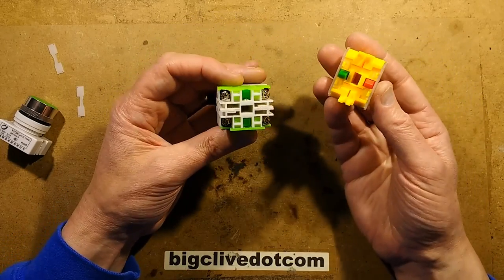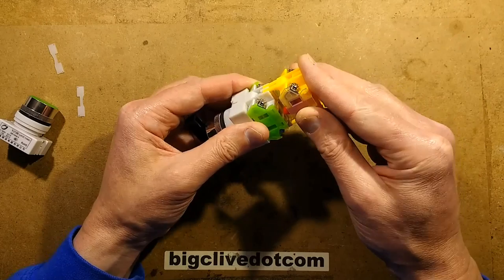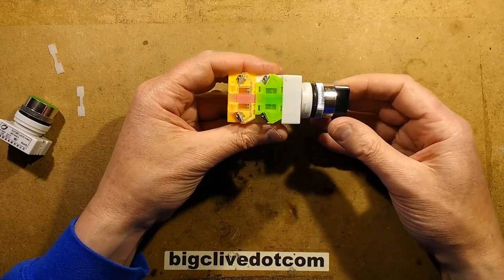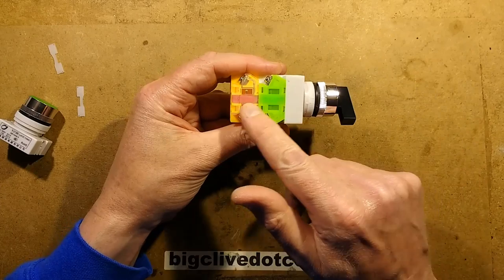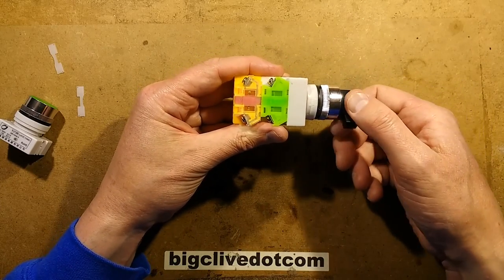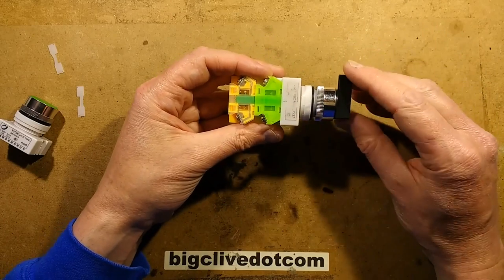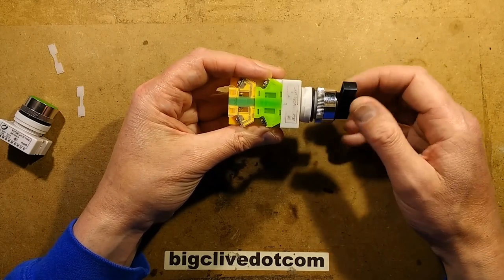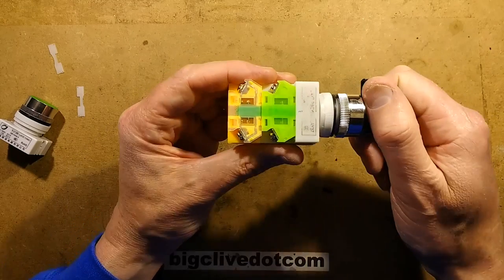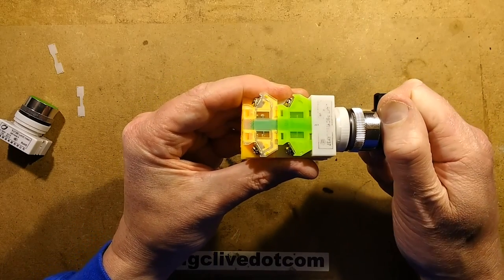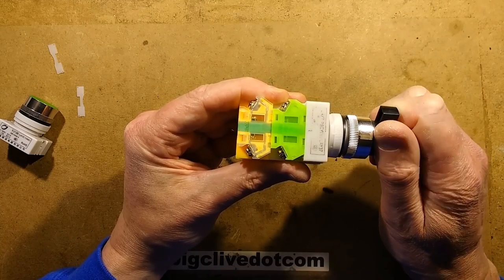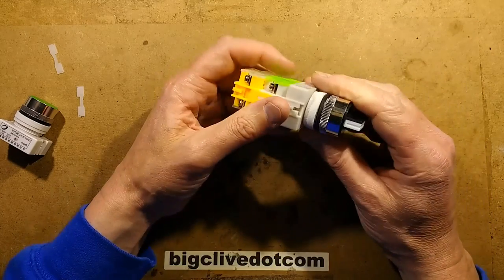The contact blocks seem to be compatible amongst them all, and you can therefore just slide another block in the back. I wouldn't stack them too high, but this means that when you stack that on, the plungers push right through. So you've got this normally closed contact now that opens in that position, and this one's now got two normally open contacts that close. It's making contact and then the movement continues down the spring to actually make sure it's a decent contact. So they seem okay that way.